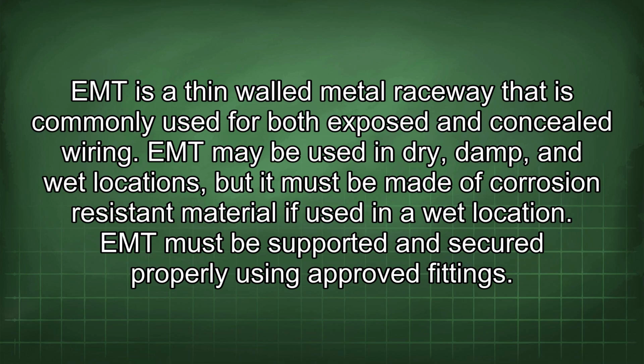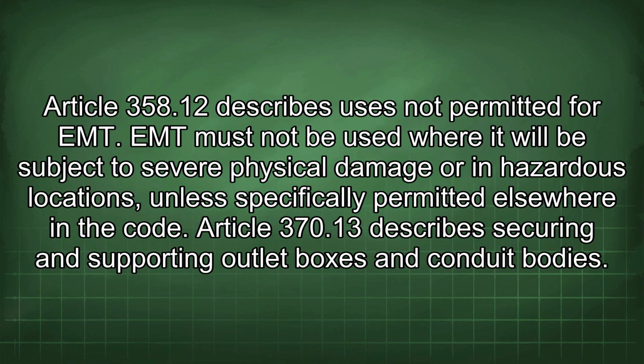EMT may be used in dry, damp, and wet locations, but it must be made of corrosion-resistant material if used in a wet location. EMT must be supported and secured properly using approved fittings. Article 358.12 describes uses not permitted for EMT. EMT must not be used where it will be subject to severe physical damage or in hazardous locations, unless specifically permitted elsewhere in the Code.